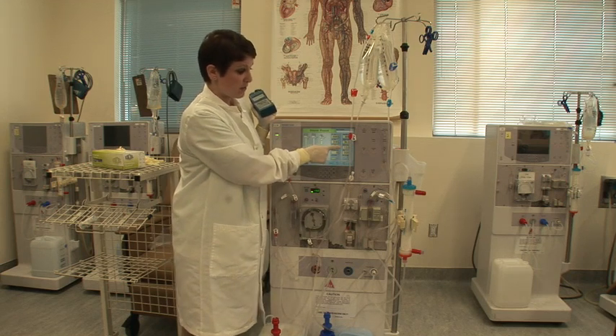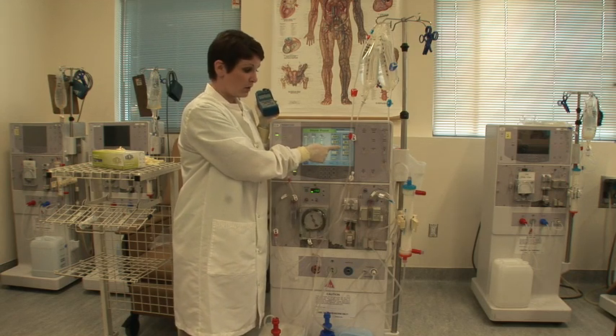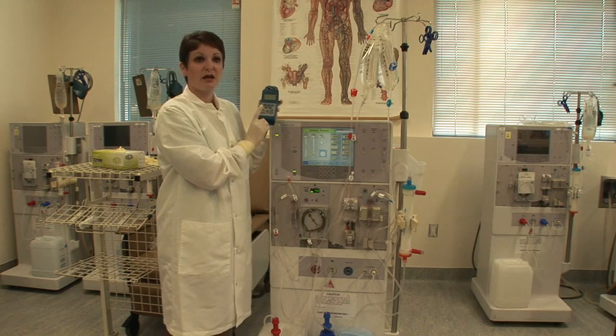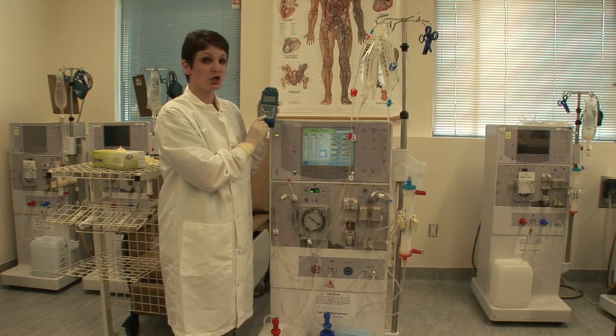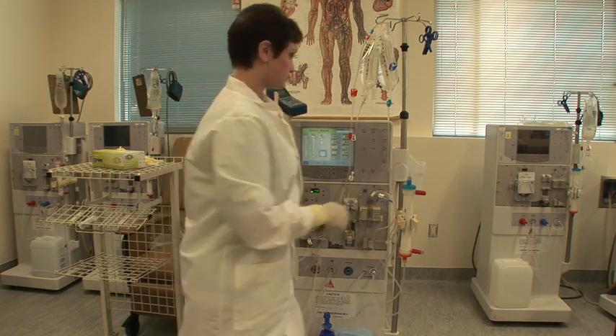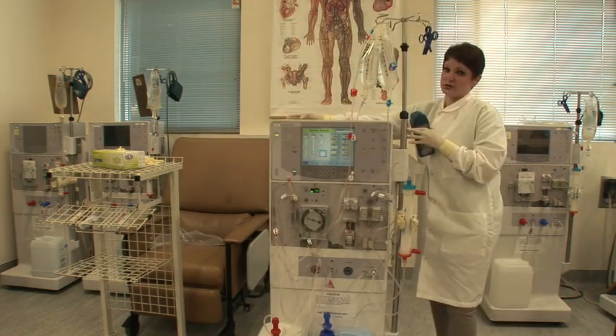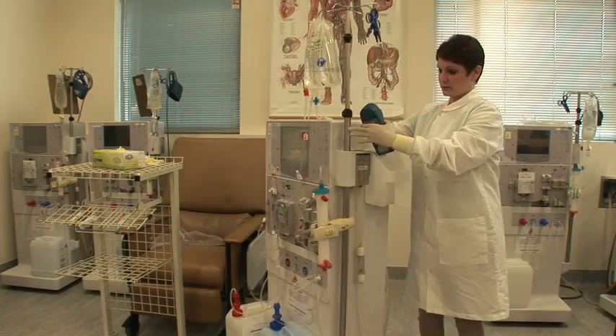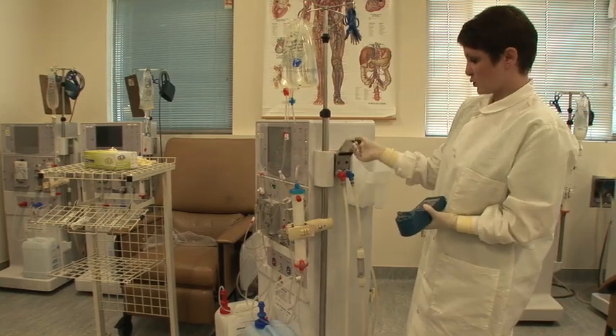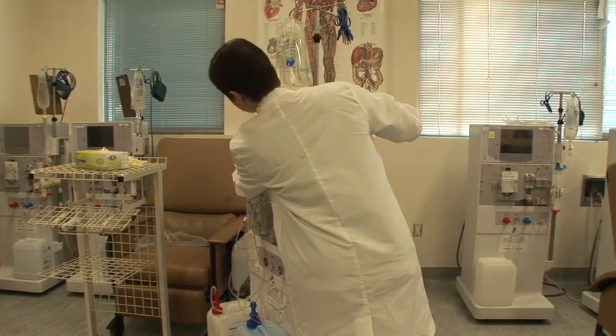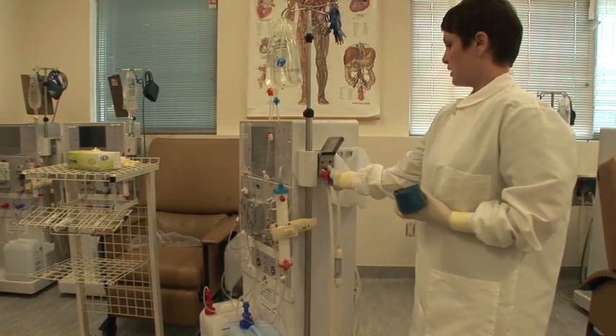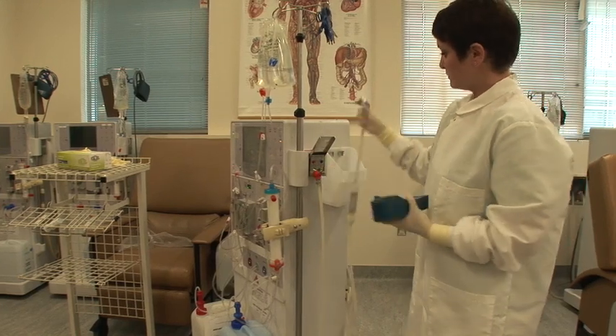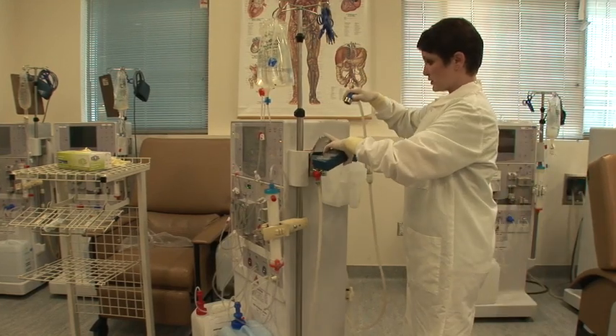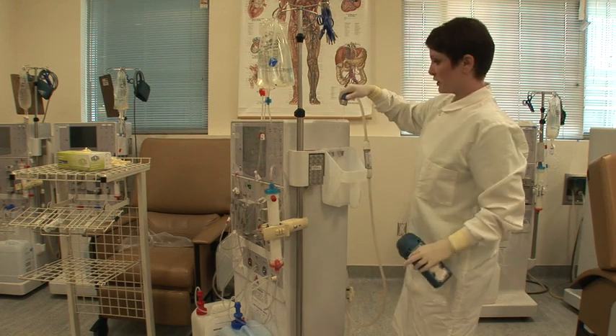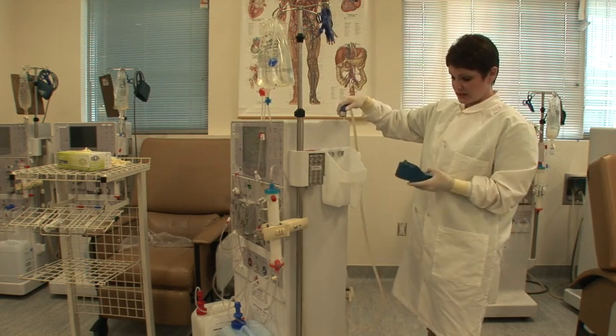So my conductivity on my machine is 13.0. I need my Myron L to say anywhere from 12.8 to 13.2. I'm going to turn the machine so that you can see this well enough. You're going to open the Hansen door, and I'm going to mute that alarm. And you're going to remove your dialysate connector and close your door. That's going to allow the fluids to flow that you need to test.